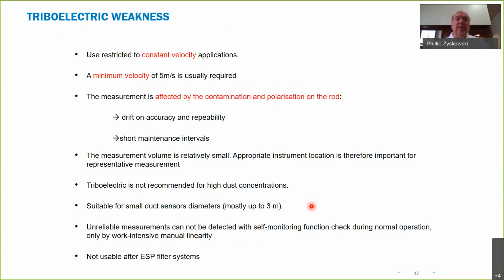So there's a velocity weakness. For tribo flow, you need to have a continuous velocity. There's a contamination issue often that causes drift for the accuracy and the repeatability as dust particles cake up on the rods. And often this requires maintenance. Someone's got to clean the rods. So for high concentrations, typically tribo flow doesn't work very well. It is suitable for really small duct work. And I showed you that earlier, that little self-check we do. There is really no way to do that with the tribo flow type technology.